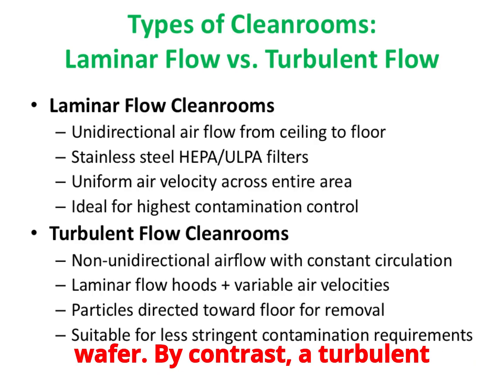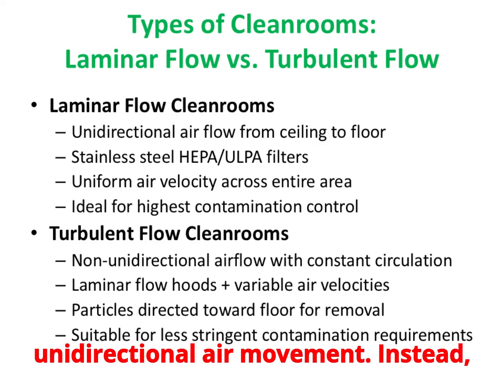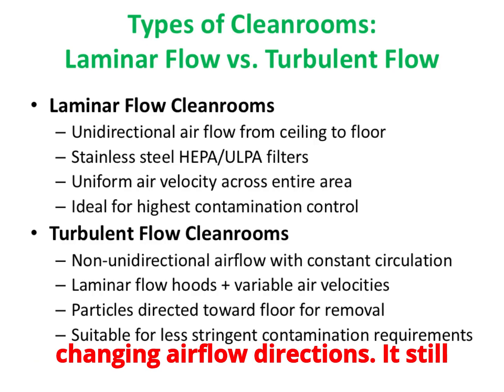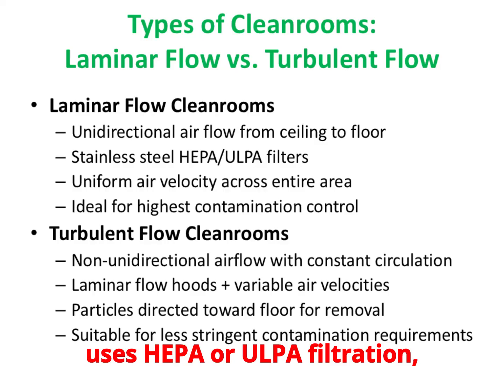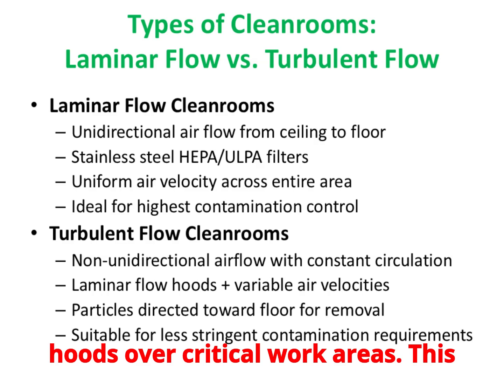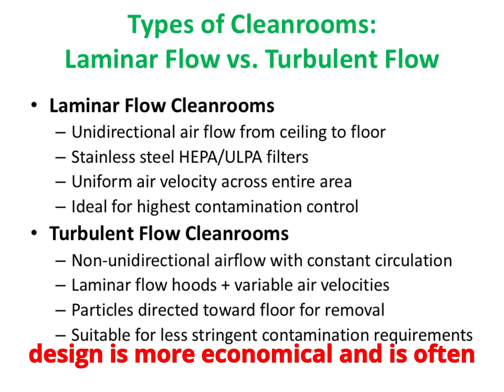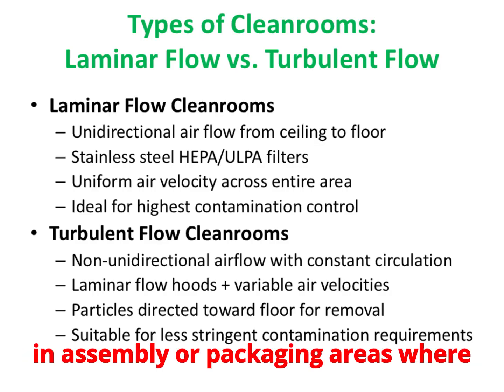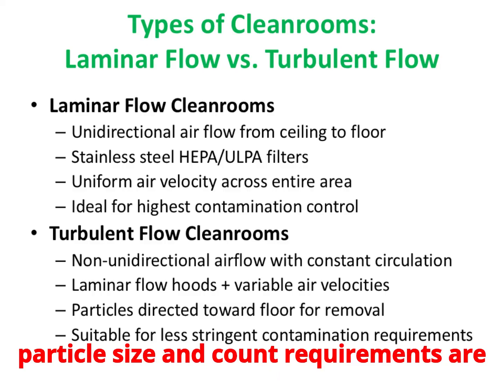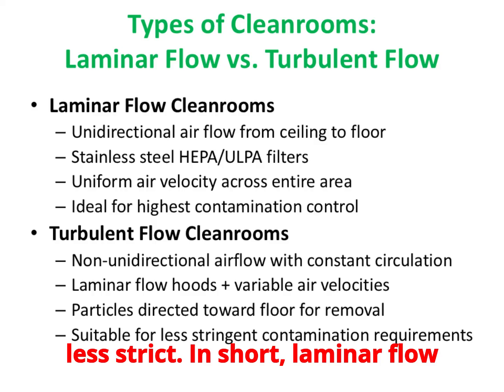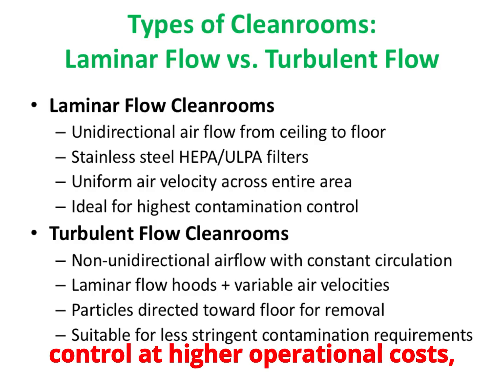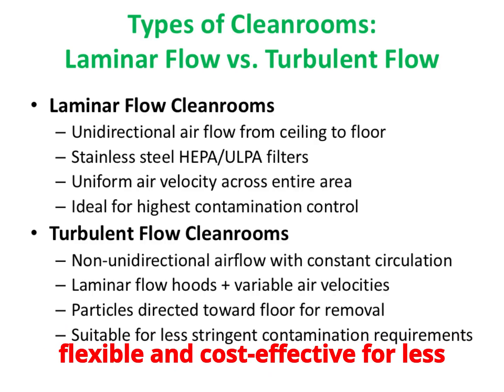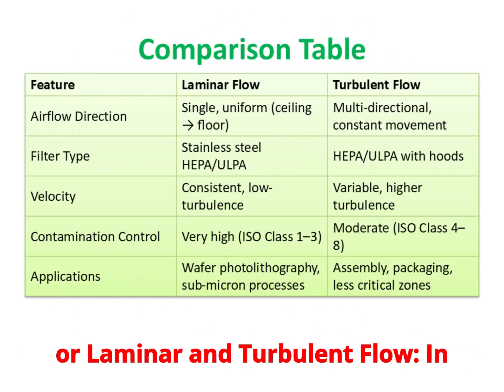By contrast, a turbulent flow clean room does not rely on unidirectional air movement. Instead, it maintains constant circulation with changing airflow directions. It still uses HEPA or ULPA filtration, but often with localized laminar flow hoods over critical work areas. This design is more economical and is often used for processes with lower contamination sensitivity — for example, in assembly or packaging areas where particle size and count requirements are less strict. In summary, laminar flow clean rooms provide extremely high control at higher operational costs, while turbulent flow clean rooms are more flexible and cost-effective for less critical environments.